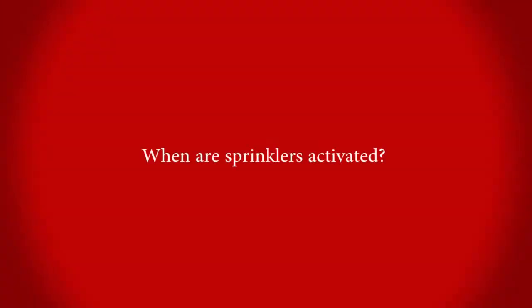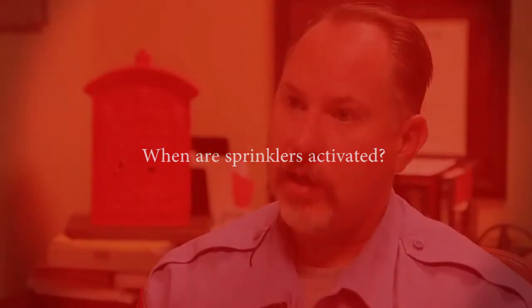examined. Sprinklers are only activated by heat. Each sprinkler head is heat rated. So most of your heads in your business occupancies are about 165 degrees. Now, we've talked many times about the misnomers of sprinkler systems. When one sprinkler head goes off, it's only the affected head, the head that's affected by the heat source, that goes off. They don't all go off.